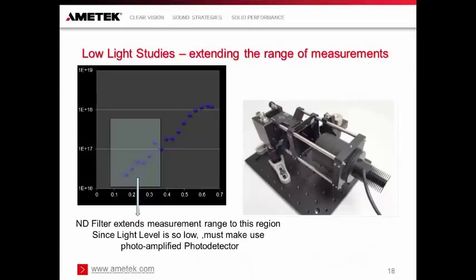So as an example of how low light studies can help extend the range of measurements, this is some data from a typical type of measurement using the neutral density filter. This is the optical arrangement. The optical bench is exactly the same size as an Apple iPad, which gives an indication of the compactness of the optical design. And incorporated in the design, we have this neutral density filter, which is in the path of the light beam. Therefore, we can calibrate the effect the neutral density filter has upon the light intensity.